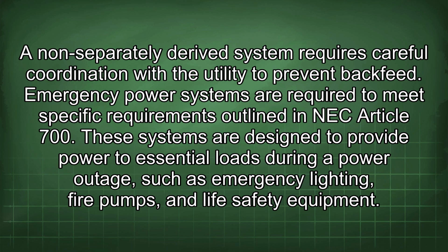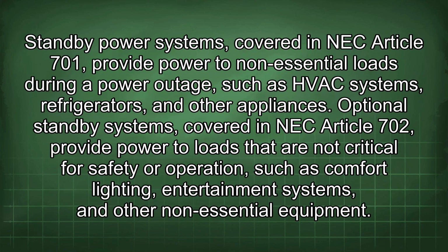Emergency power systems are required to meet specific requirements outlined in NEC Article 700. These systems are designed to provide power to essential loads during a power outage, such as emergency lighting, fire pumps, and life safety equipment. Standby power systems, covered in NEC Article 701, provide power to non-essential loads during a power outage, such as HVAC systems, refrigerators, and other appliances.